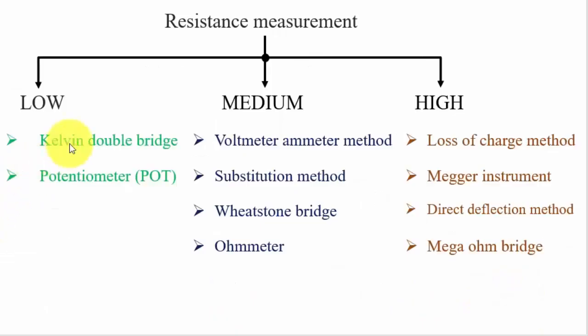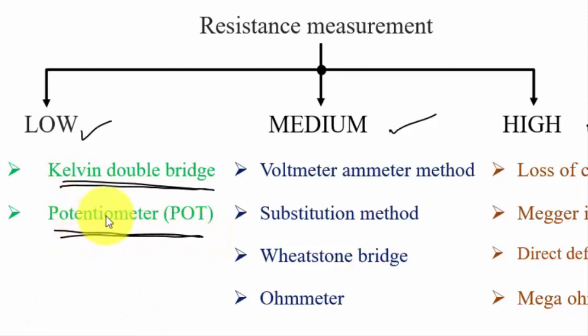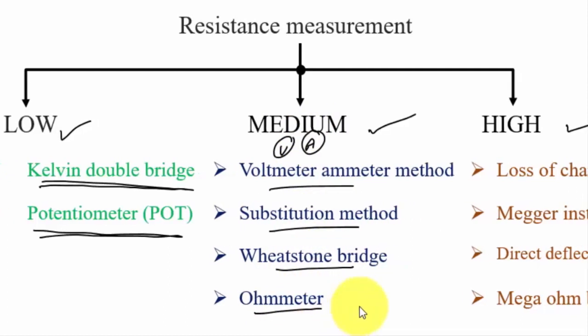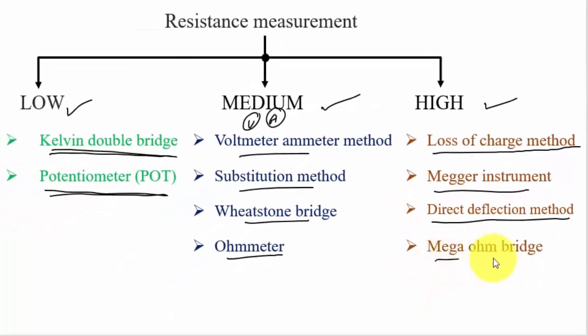For resistance measurement: low value resistance — use Kelvin's double bridge or potentiometer. Medium value resistance — use ohmmeter, ammeter-voltmeter method, substitution method, Wheatstone bridge. High value resistance — use loss of charge method, Megger instrument, direct deflection method, or mega ohm bridge. For engineering service exams, the Megger instrument topic is very important.